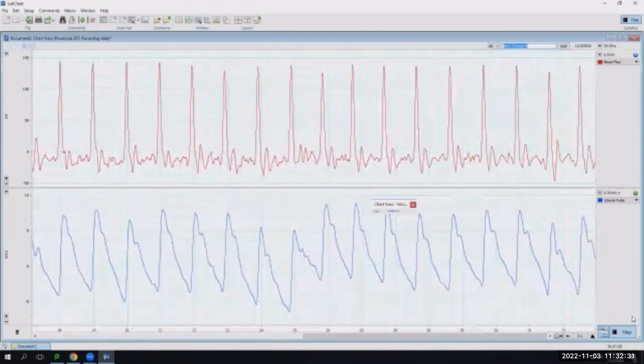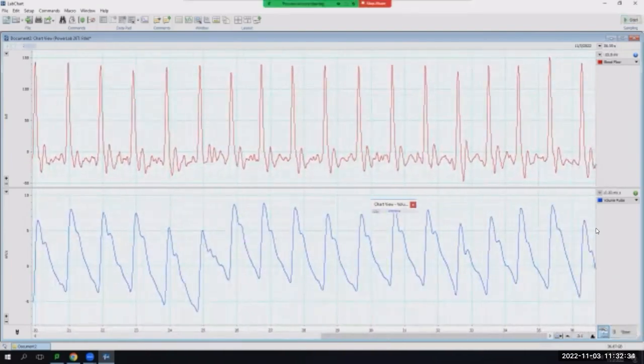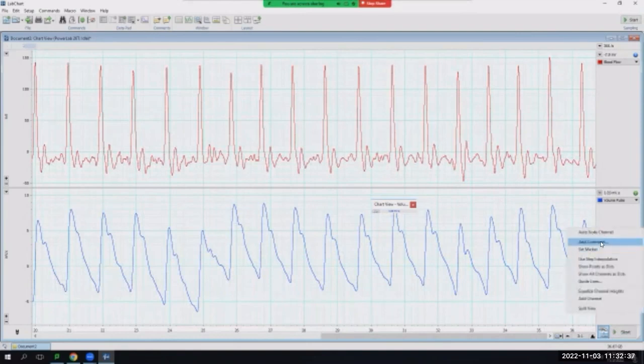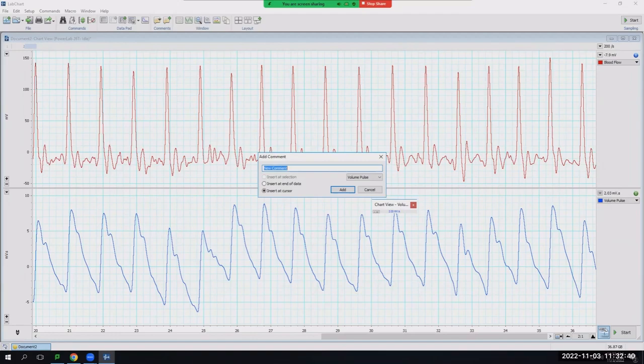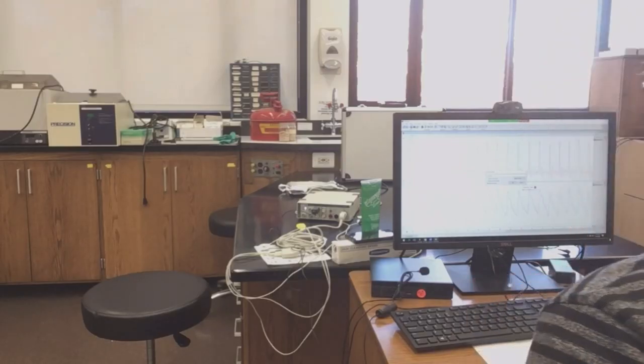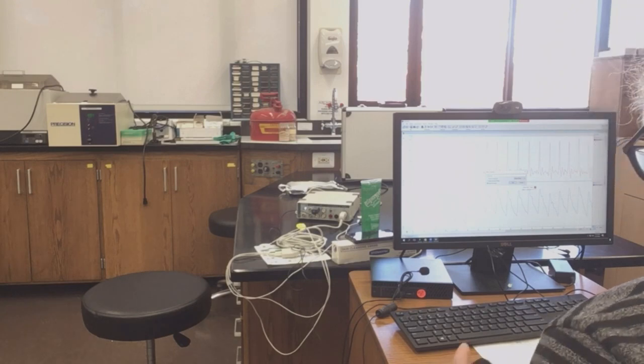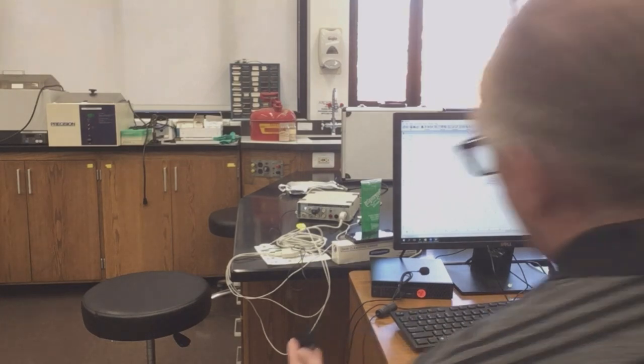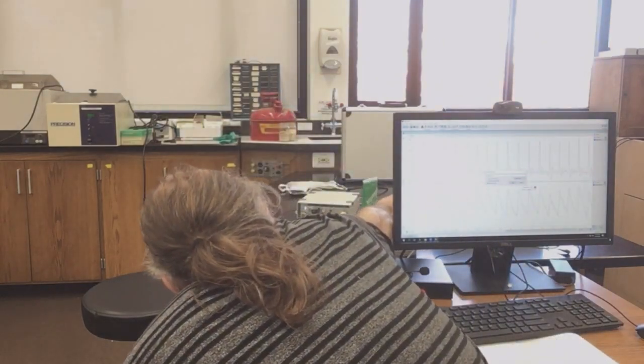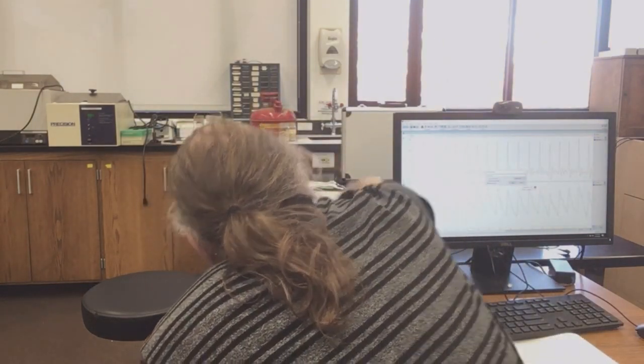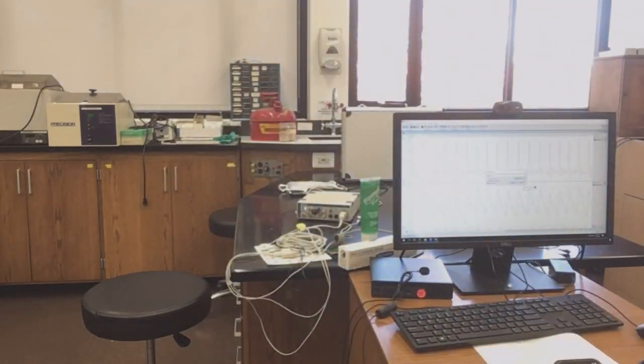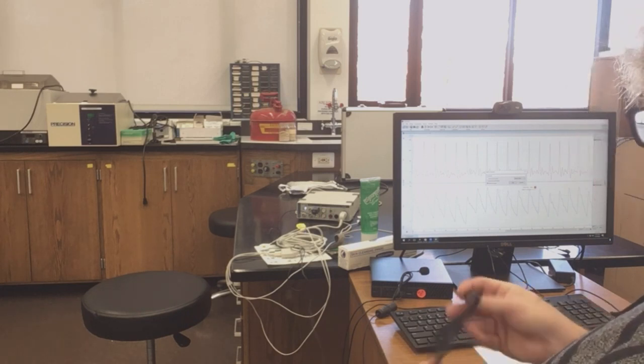So I'm going to stop the recording. We're going to prep a comment, and we're going to add the comment recovery. Then you want the individual to squeeze either the hand dynamometer or some other object they have present with the hand that has the pulse transducer on it. Basically a squeezing activity. Again, don't put any pressure on the pulse transducer itself. So I can set my stopwatch.